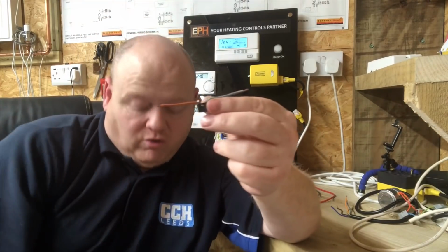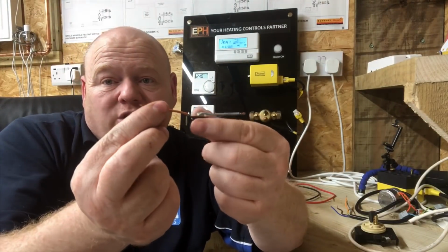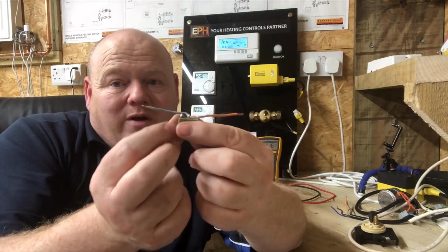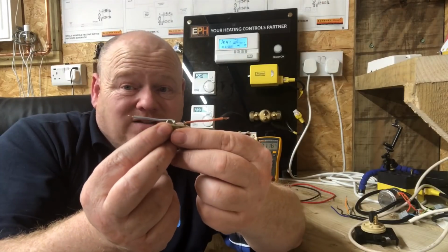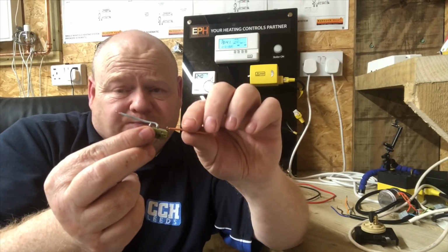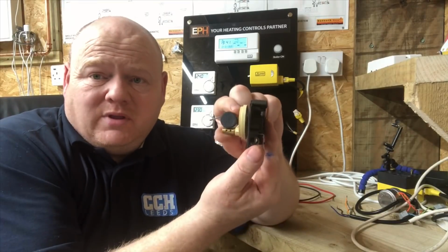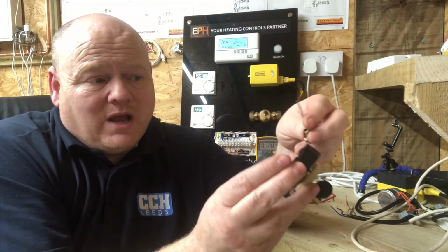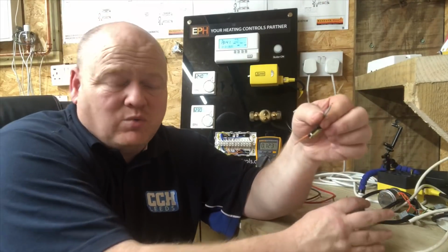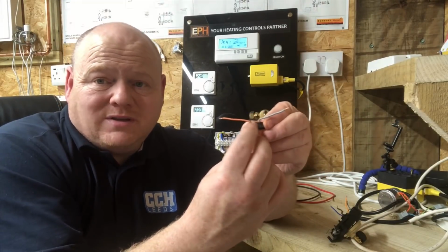Whatever we have on one side of this wire depends how it's wired, so some people will say your orange will go to the boiler, but sometimes it's wired the opposite way around. It doesn't really matter as far as I know, because all this is just a switch. So what happens is these cogs move here, it's opened that valve, and at the same time this cog here, this part of it, touches the micro switch, and it pushes the micro switch, and that opens that connection there.